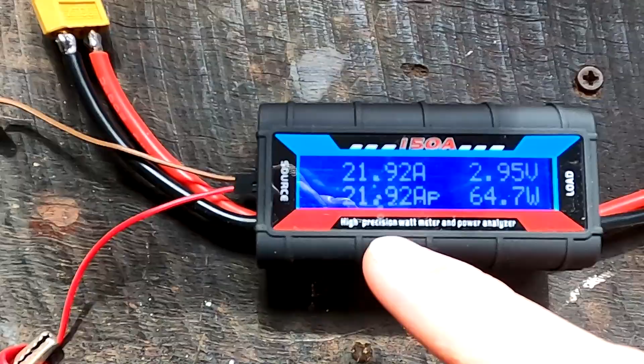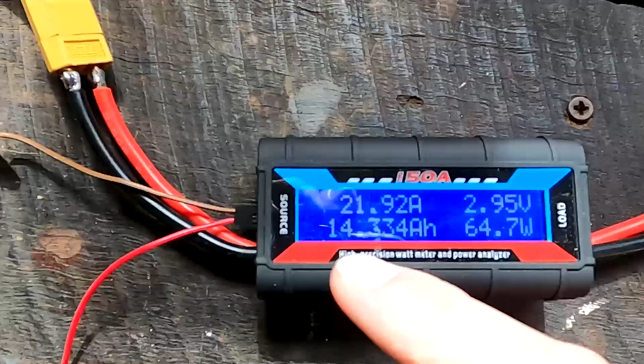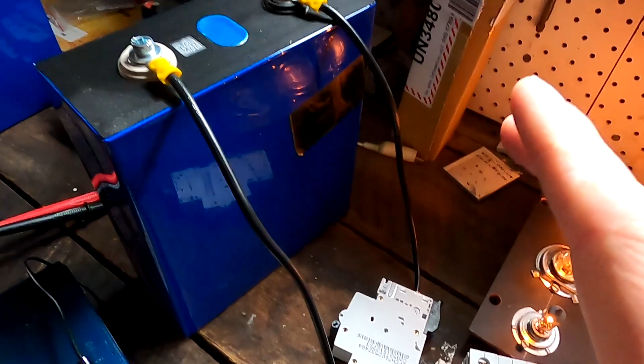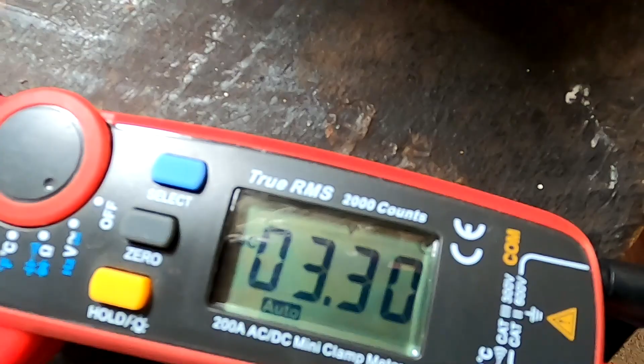Okay, so we are now 14.3 ampere hours into the test of the projected 280 ampere hours. And I just measured the voltage again here on the battery directly, and we've got 3.3 volts. This is quite normal - when the battery is fully charged it shows 3.65 volts, but then you put some load on it, or even take the charger away, and the voltage will drop.